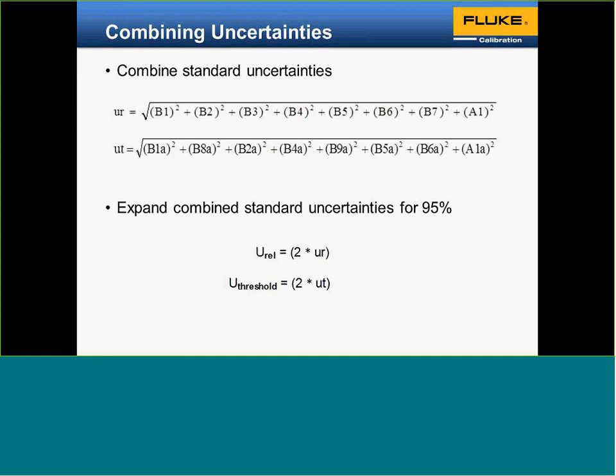Down the list of all the parameters for the relative section and the threshold section. The URs on the top line are the relative uncertainties and the threshold uncertainties. The idea is they're all at one deviation, or one standard uncertainty. We're going to combine them all by root sum of squares, RSS. All combined through RSS, we can find the 95% confidence level.